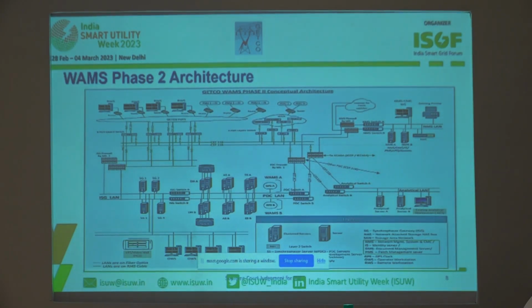This data will go to the PDC, where we have different servers like application servers and synchrophasor servers, and that data will go to the historian server, which will have a capacity of 1,000 terabytes. All servers have redundant facilities, and all data comes through cyber security via firewall, and from the synchrophasor gateway it will be available to the remote workstation.